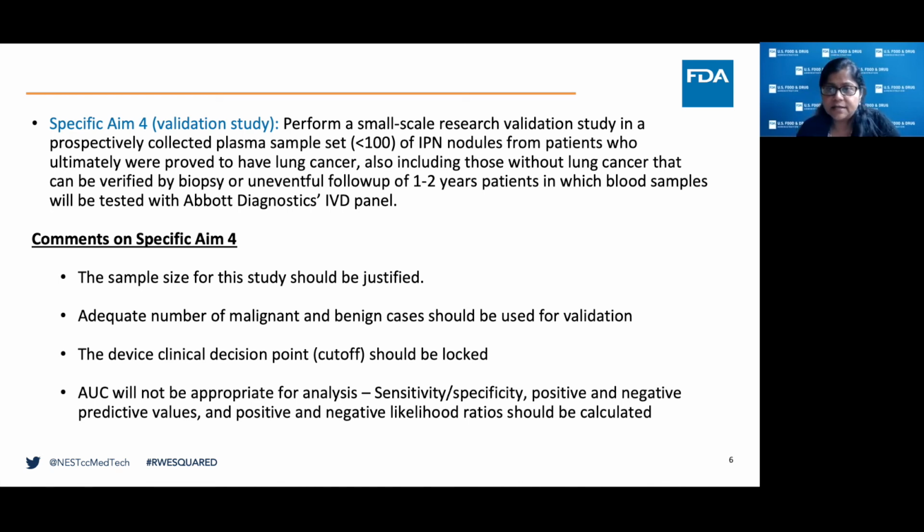were not clearly outlined. Also, we wanted to understand whether adequate number of malignant and benign cases were used for the algorithm validation. Also, it was not very clear whether the clinical decision point or the cut point of the assay was locked after establishment of the algorithm.